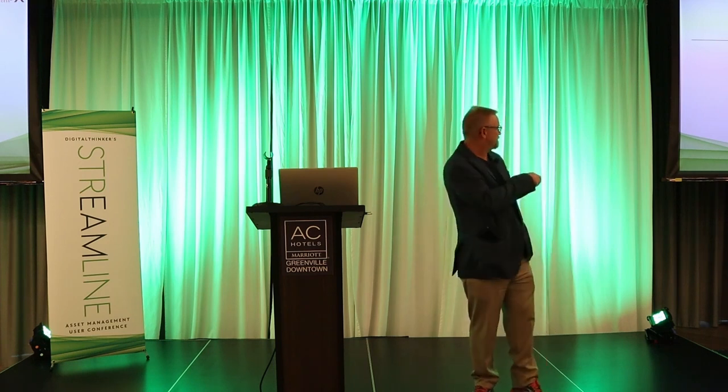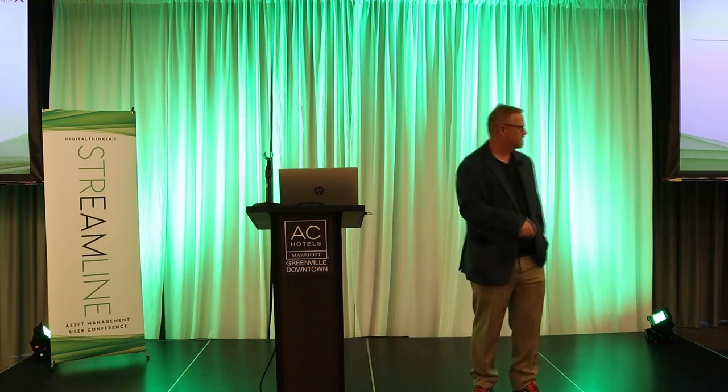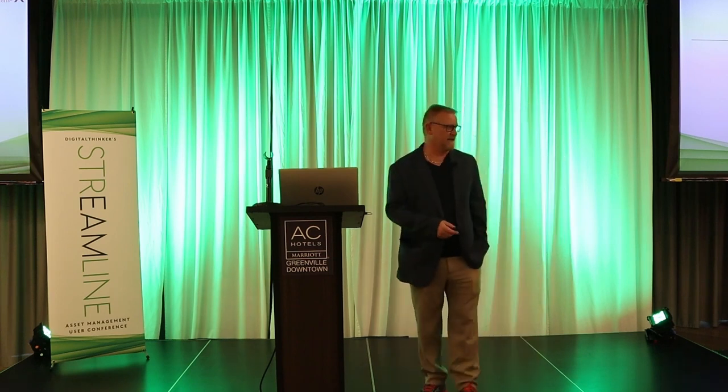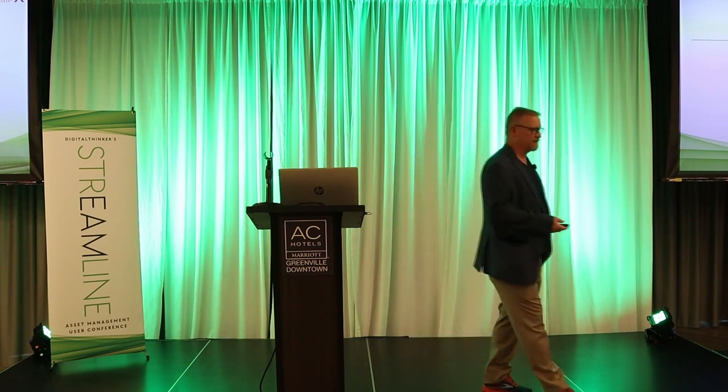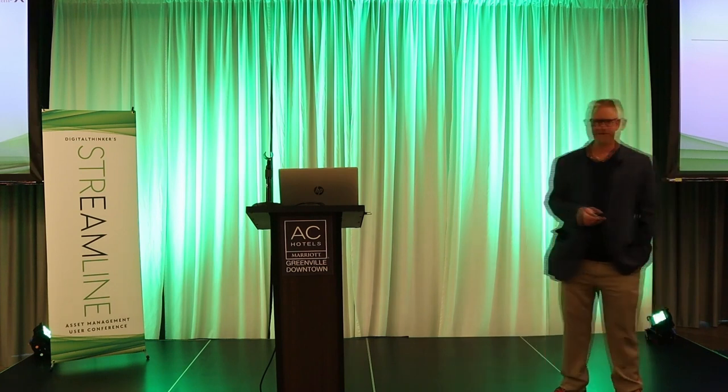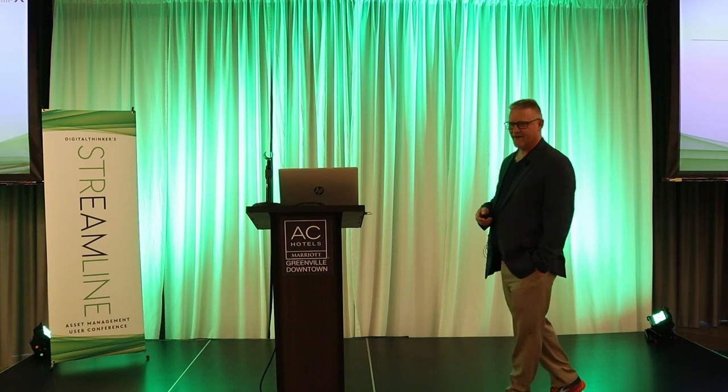There's the light post he was standing next to. He was standing right here. We dug one hole. Garden hose size leak in a 14-inch condensate return line. That's what happens when they backfill on Saturday, and no one's there to witness it.